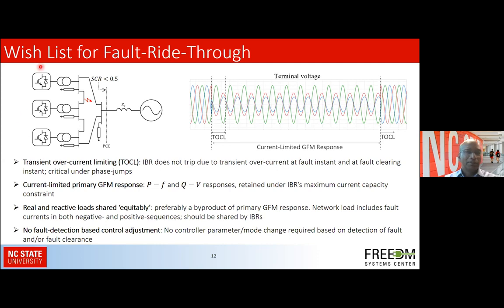And all of the IBR resources here, ideally all of those that are GFM type inverters, should be able to share equitably the real and reactive power loads, which would preferably be a byproduct of the primary GFM response. And note that when there is a fault, these units, in addition to supplying the regular load current, must also support the fault current. And it's ideal if all of the resources can share in that fault current. And then the fault management algorithm should not be based on the fault detection method, because we don't want any parameter changes or gain changes, so that we are seamlessly able to come out once the fault is cleared and go back into normal operation.